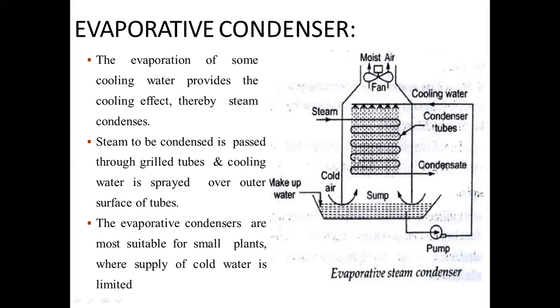This type of condenser is used where there is a scarcity of water, or water is available in very small quantity. In this case, steam is supplied through the pipe. You can see steam is inside the pipe, and water is supplied with the help of a pump, and water is sprayed with the help of nozzles. The water comes in contact with the hot pipes, and some water gets evaporated, which can be removed with the help of a fan.